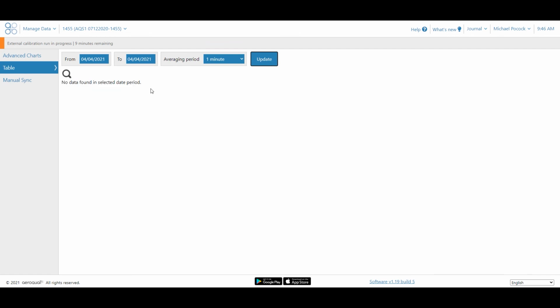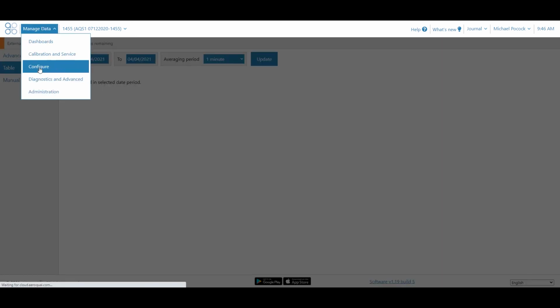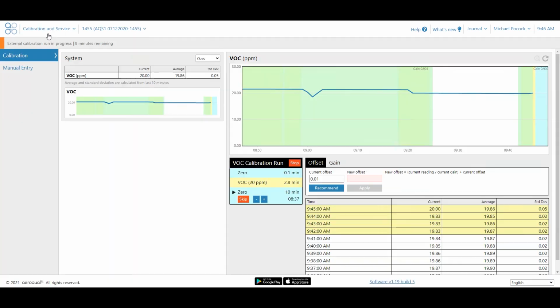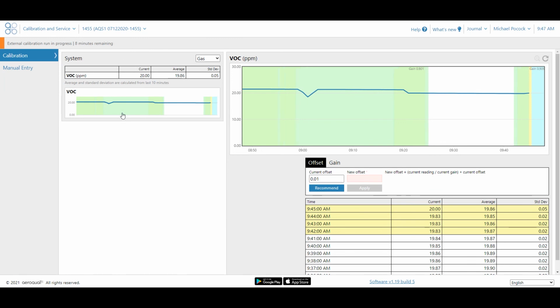So you could do a quick calibration check of the system with your span gas cylinder, or you can go through the full calibration that I just showed you, doing the 0 gas and the span gas. Remember, if you're finishing your calibration, to stop the calibration run and also stop being in service mode. You don't want to be in service mode anymore, because you've done your calibration and you want the data to be valid again and part of your data set. I did do that small adjustment on the gain, so that changed to 20. So there you go. That's how you calibrate this module.